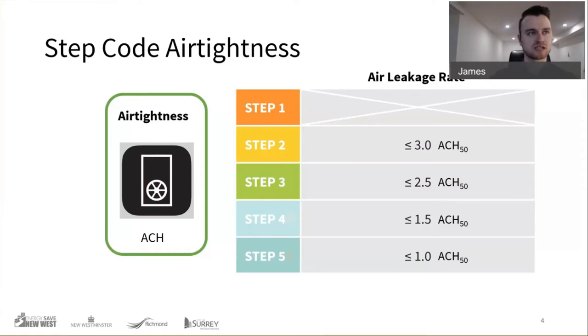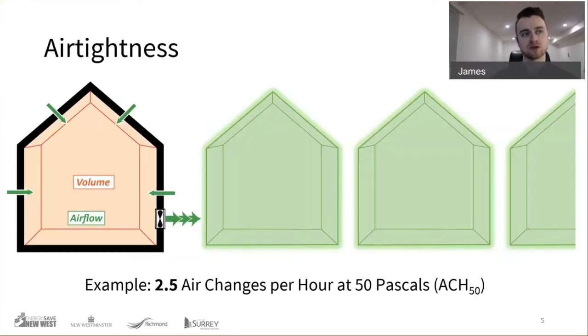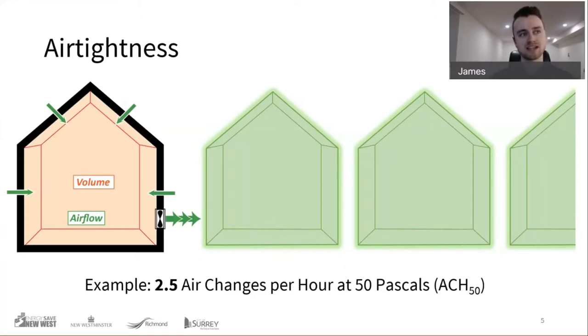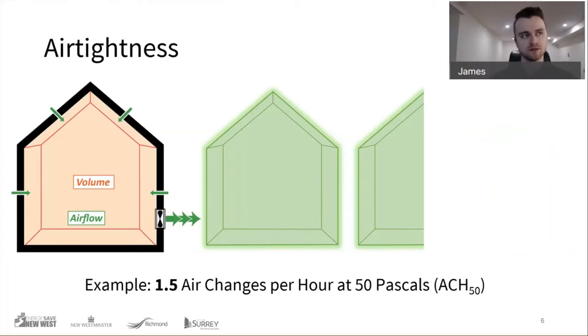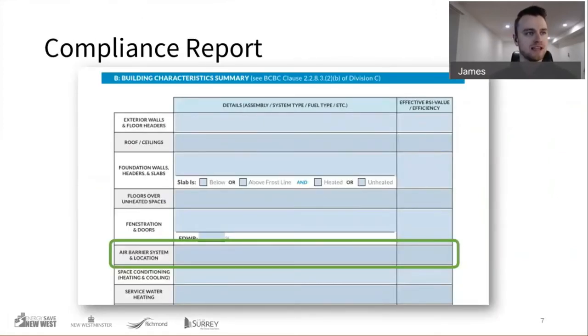To illustrate the numbers: at step 3, that's 2.5 ACH50, meaning over the course of an hour you would have transferred two and a half times the volume of the building at the test pressure. Stepping down to 1.5 means less airflow and less volume. Compliance with the step code also requires noting what the air barrier system is, besides the target number. The goal is to make the building airtight.